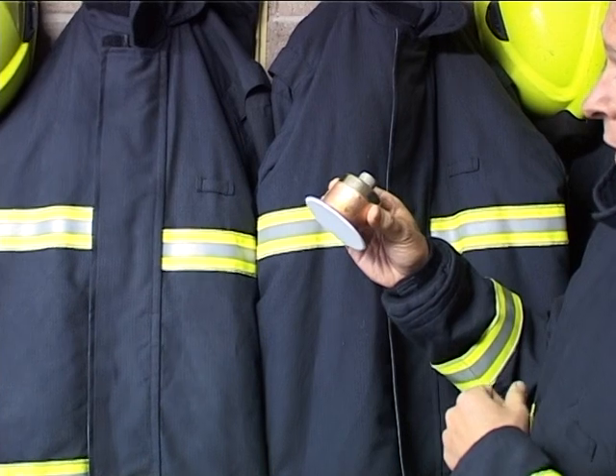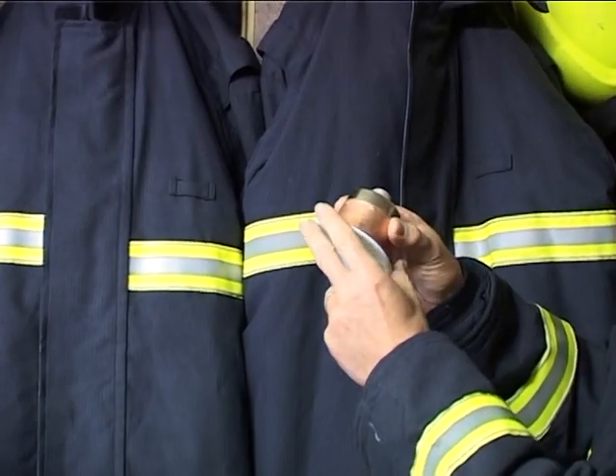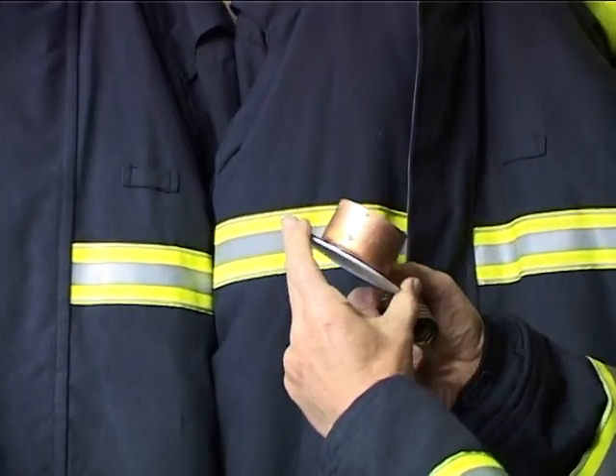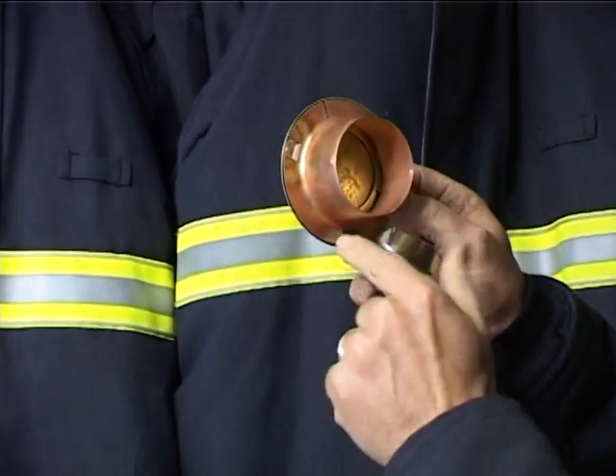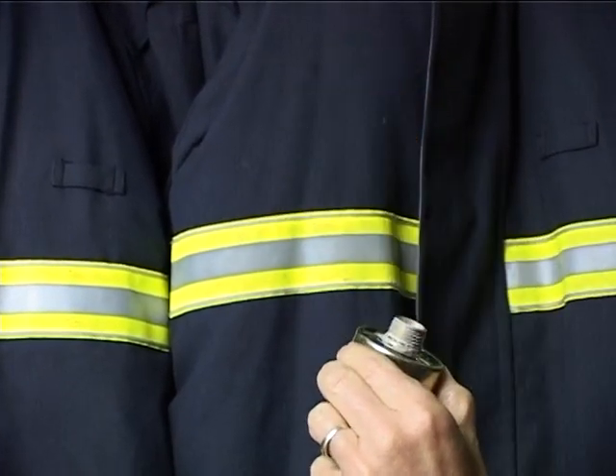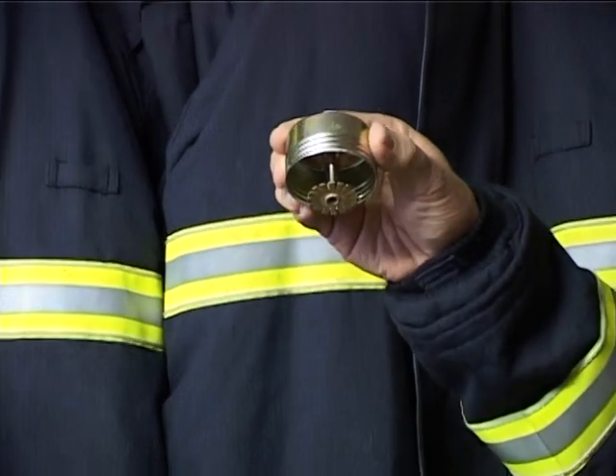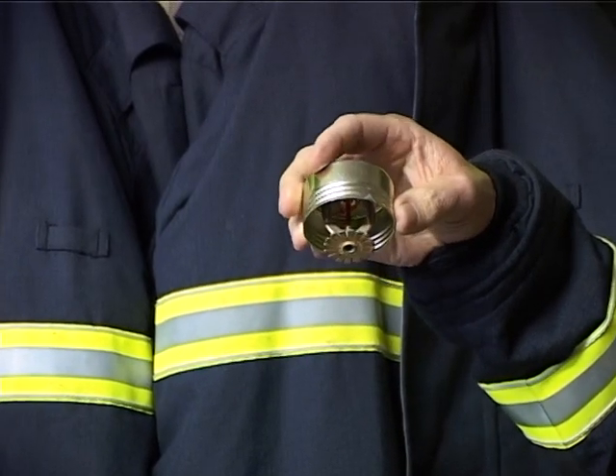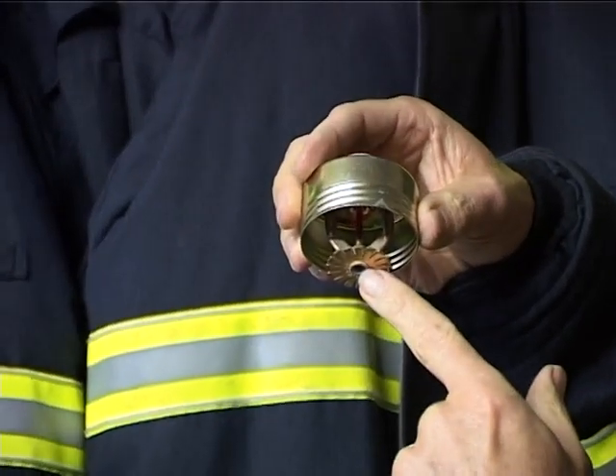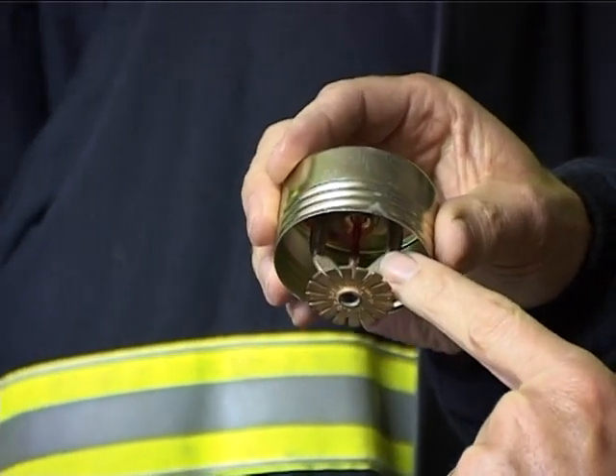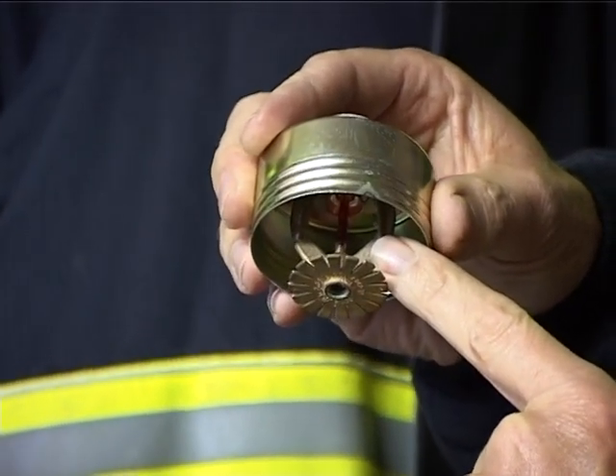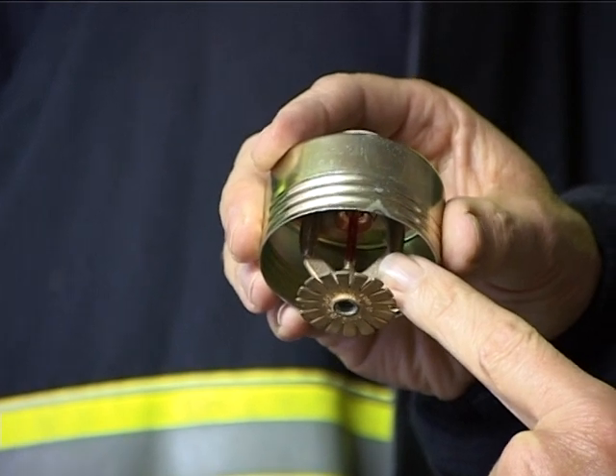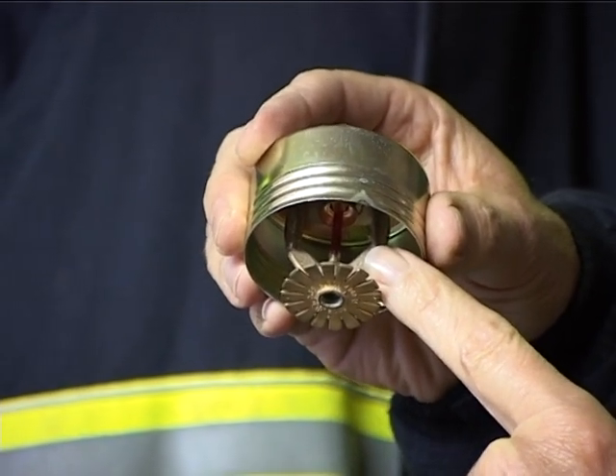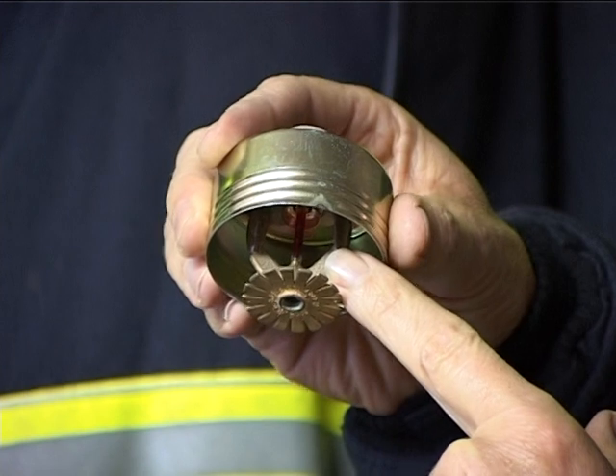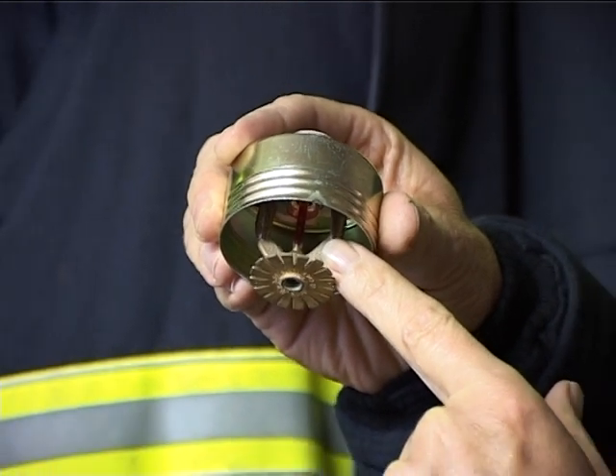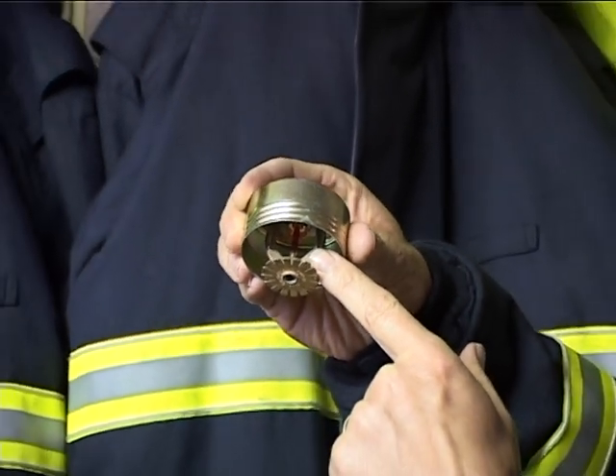When the heat from the fire gets to about 50 or 60 degrees at ceiling temperature, there's three little solders which will melt and the blank plate will actually drop to the floor. And then that exposes the sprinkler head itself. And what we have here is a deflector plate and inside a small glass bulb. In the bulb there's fluid and an air bubble. When the heat from the fire makes the fluid expand, it contracts the air bubble and eventually pressure will build up inside the bulb and it will break.